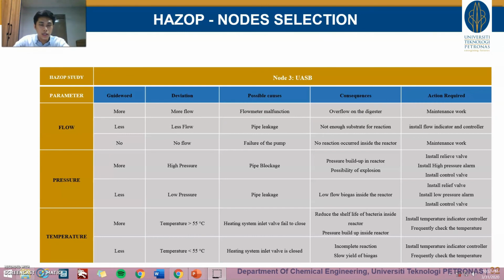Next is UASB. For the flow parameter, the deviation for more flow is caused by flow meter malfunction. Consequence, overflow on the digester. Action required is to do the maintenance work. Less flow, the cause is pipe leakage. Consequence, not enough substrate for reaction, and action required is to install flow indicator and controller.